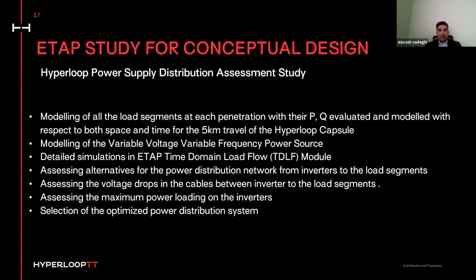ETAP study for conceptual design. We already started designing. We started from the power distribution part between the inverters and the linear motors. We have segmentation for the linear motors along the track. Different segmentation, different lengths from 100 meter to 300 meter, which basically creates different active and reactive power needs. So ETAP started modeling of those loads for us. Detailed simulation in ETAP time domain and doing a load flow is another work that ETAP is in the process of. They are helping us with the trade-off study on AC distribution versus DC distribution along the track for powering the propulsion system.